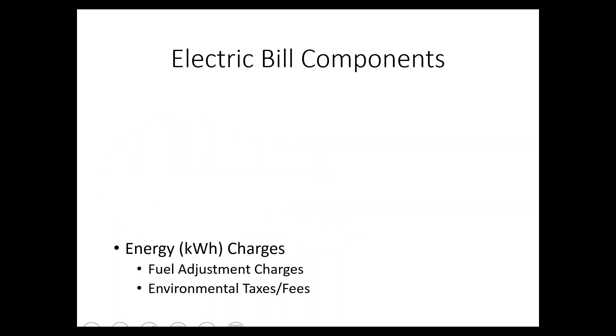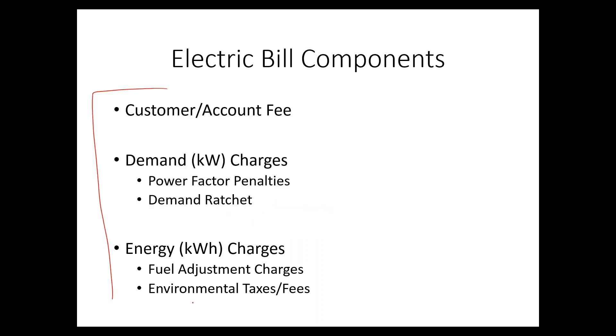The same time-of-use concept applies to kilowatt-hours. Some utilities don't charge demand at all but instead charge very high kilowatt-hour prices when you take energy during certain hours — primarily the afternoon. For comparison, if you use energy at midnight you might pay one price, but it could be five times more expensive to use the same amount of energy at 4 o'clock in the afternoon. That's a summary of the three major components of most electric bills around the world.